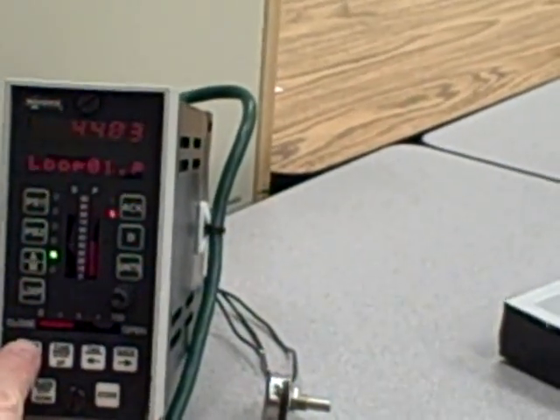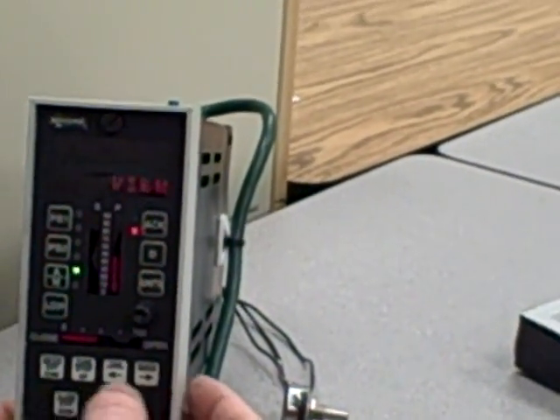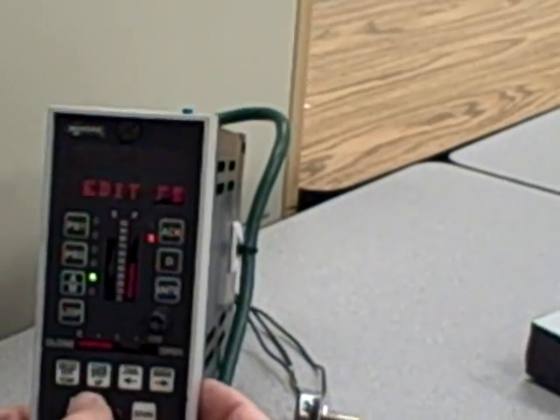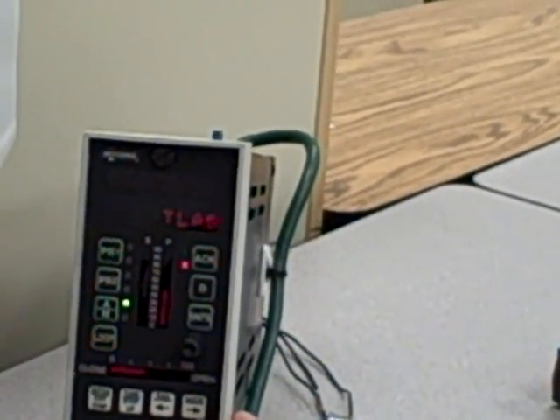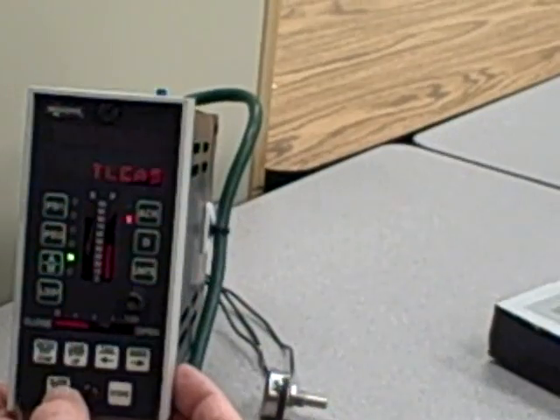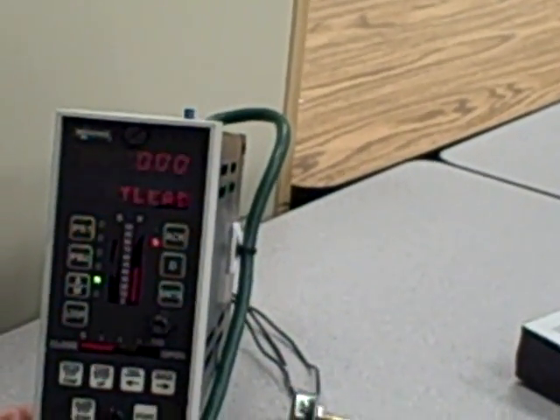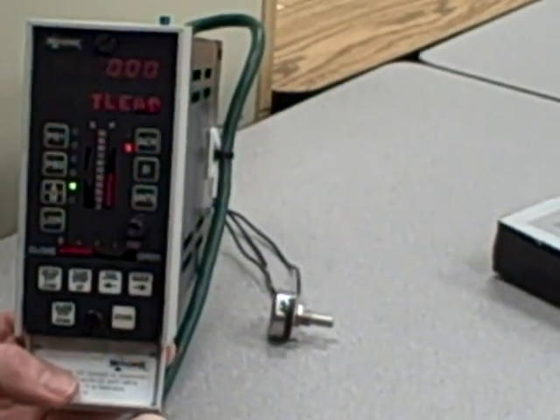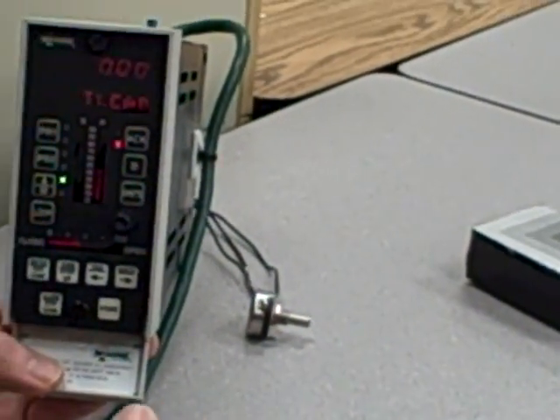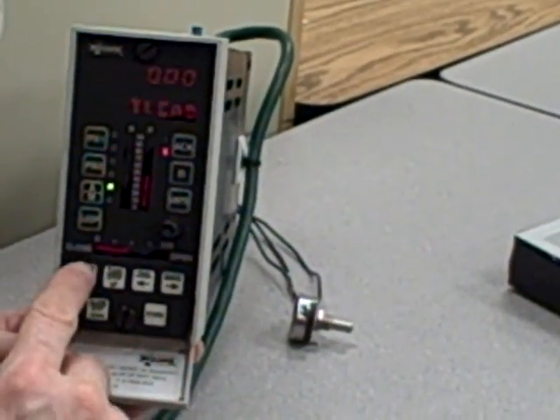So now we enter configuration. We step down. I'm going to edit that block. And what I'm going to say here is I want the lead time to now be 0. I'm going to turn it all the way down to 0 and store that value. So now it has a lag time of 0.05 minutes, a lead time of nothing. So it's nothing but lag at this point. I'm going to exit.